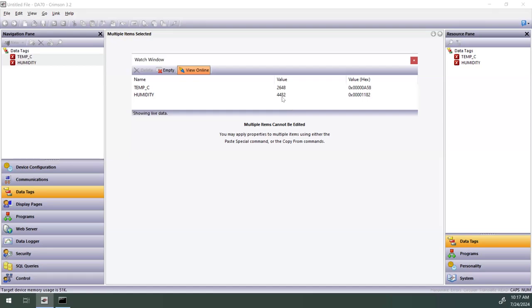I'll just draw your attention to the humidity tag here. It's currently returning a value of 4,476, right around there. In the case of both of these values, there are 2 implied decimal points, which is very common in the world of Modbus. So this value of 4459 actually represents 44.59% relative humidity. That's just something to be aware of. And I want to mention that Crimson can account for this and display it as such. But to keep us on track, I'm going to navigate straight to the MQTT broker configuration portion of this demo, and we'll get these values to an MQTT broker.